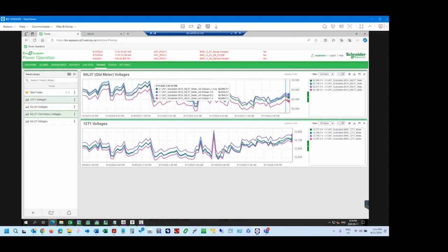But notice the front of my trend. Look how detailed that is. That's because this is two things in one. You're getting the real-time updates happening in real time, as well as that 15-minute capture going back in time. So if you leave this open as an operator screen, however big this plot goes, you will continually get much quicker samples. This is every 5 seconds, it's taking a sample.